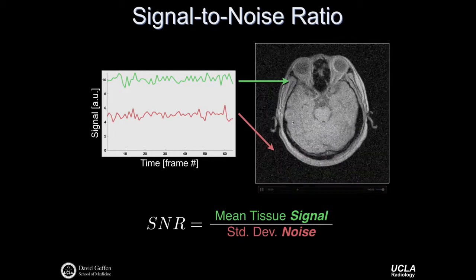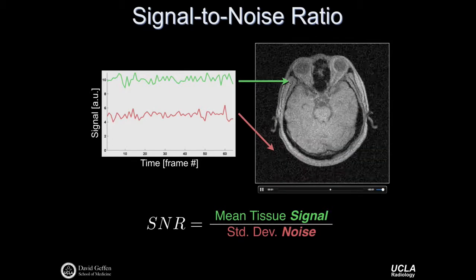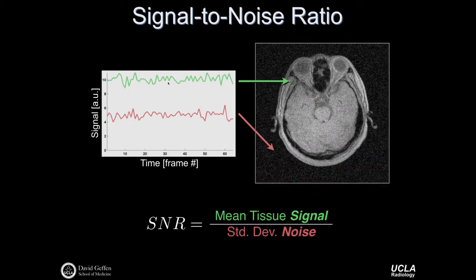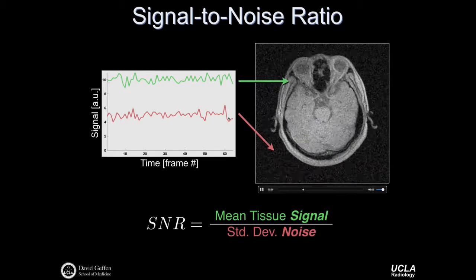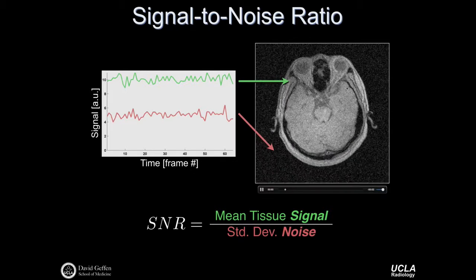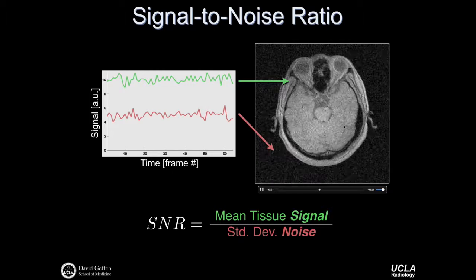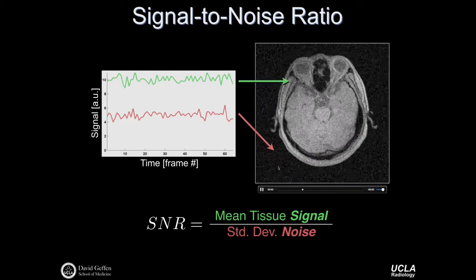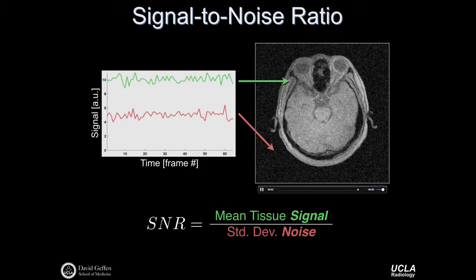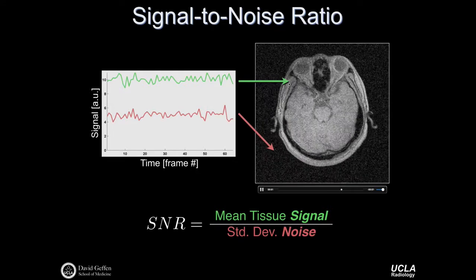In this example, we could take the mean pixel intensity for a single pixel. Since we have temporal information, we could take the mean as a function of time and calculate the noise signal in the background as the standard deviation of the signal across time. In more practical examples, we don't have a time series, so we'll typically have a single image. In that case, we can estimate the standard deviation in a region of interest outside the object in the background as representative of the noise variance, and take a small ROI within homogeneous tissue to estimate mean signal.